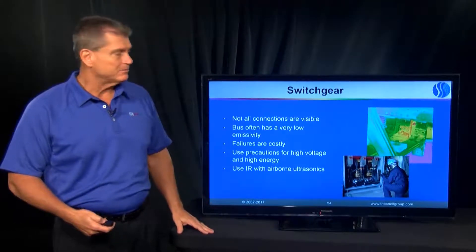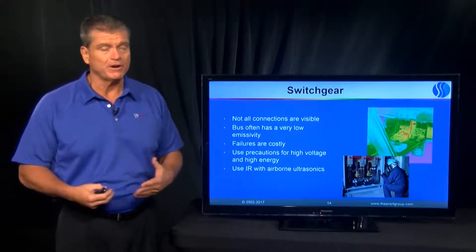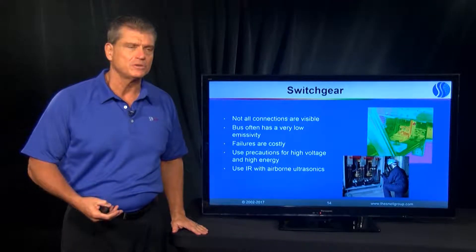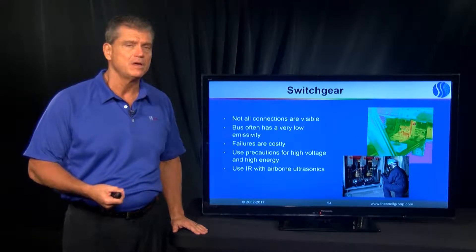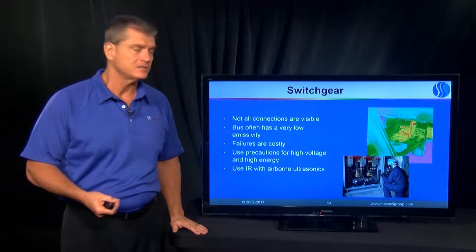Let's start with switchgear. One of the very challenging applications, also a situation where we have very high energy levels, so it may require infrared windows for much of the access to this equipment.